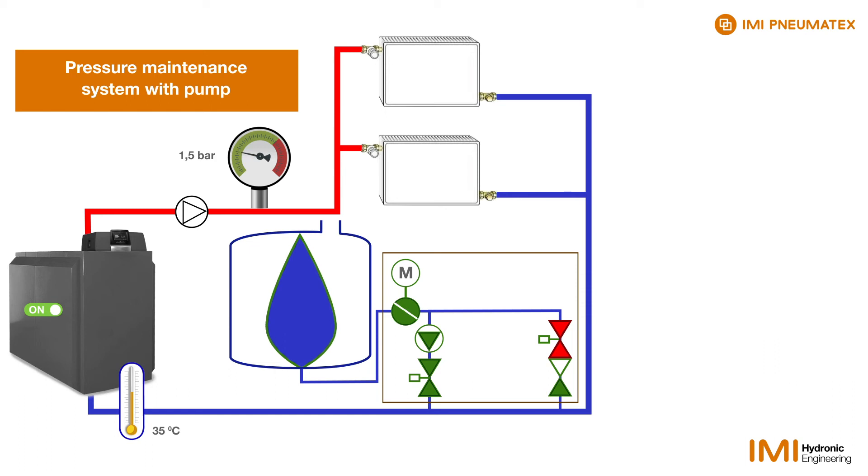It opens a motor valve and starts the pump. This pushes water out of the vessel back into the system. The system pressure increases again to 1.8 bar and the pump switches off.